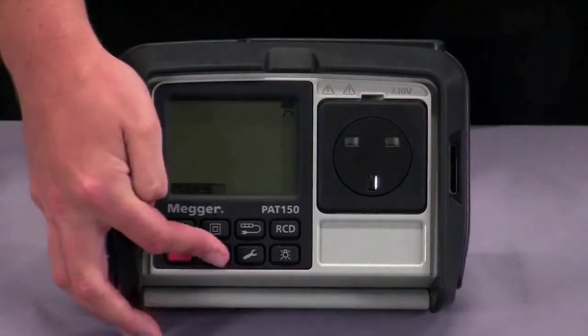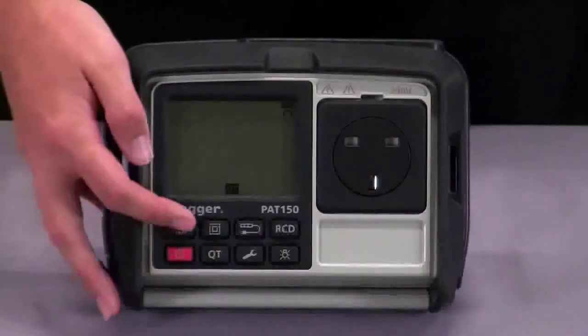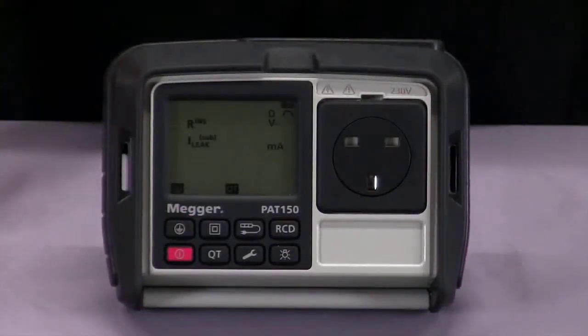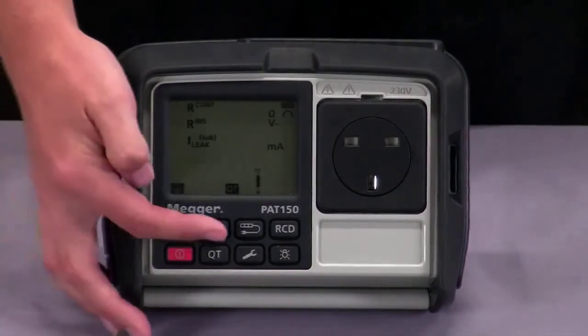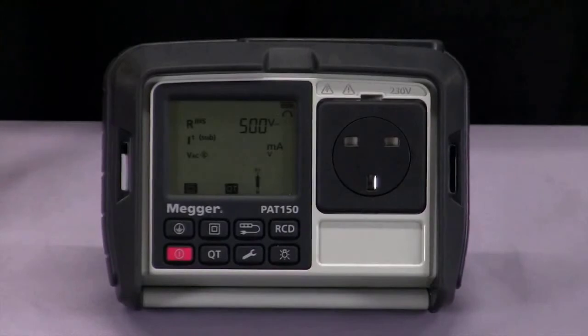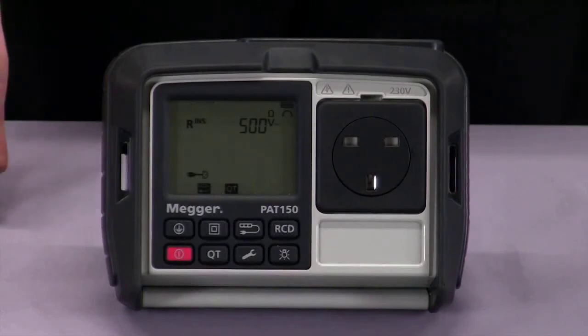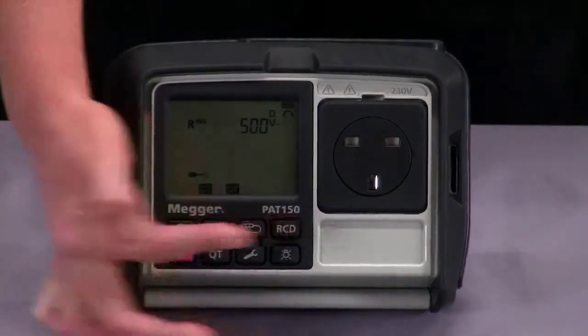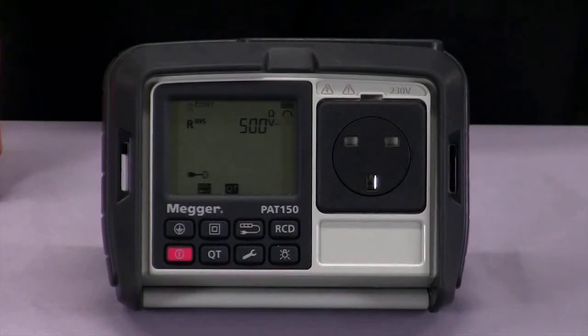Pressing the QT button takes us into the quick test mode. We can then select the Class 1 button, which gives us the option of choosing a continuity test, insulation resistance at 250 or 500 volts, a substitute leakage test, or if you've got mains connected, the mains leakage test. Pressing the Class 2 button will allow us to choose an insulation test at 250 or 500 volts, the substitute leakage test, again a mains leakage test if you have the supply connected, or SELV measurement, the separated extra low voltage. Extension lead options include the continuity test, the insulation resistance at 250 or 500 volts, and also the polarity check. The RCD button gives us the option of choosing the 30 mA or the 10 mA RCD.